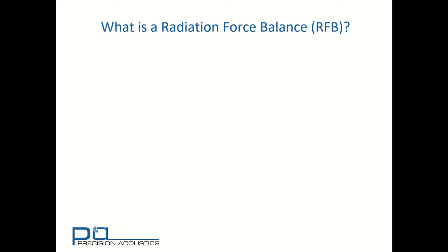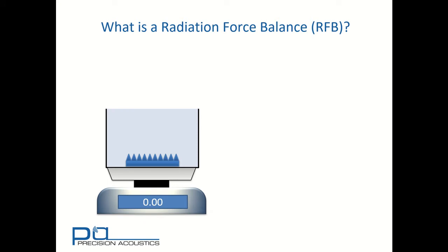A common way of determining ultrasonic power is with a radiation force balance. Let's introduce that for you. We start off with an accurate microbalance which will have a water vessel and some kind of target chain. Here we have an absorbing target, but other target types are available.